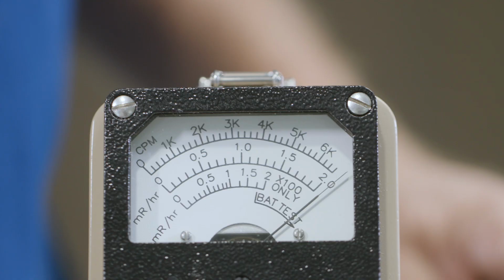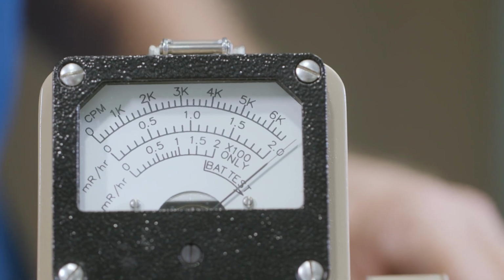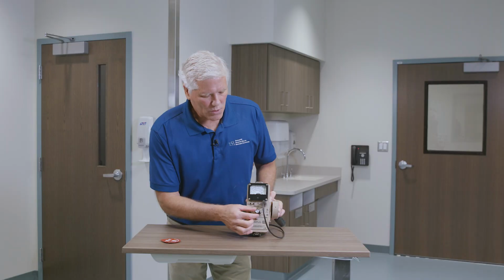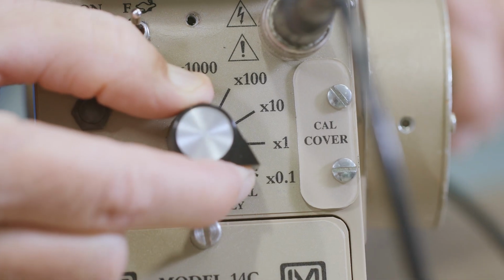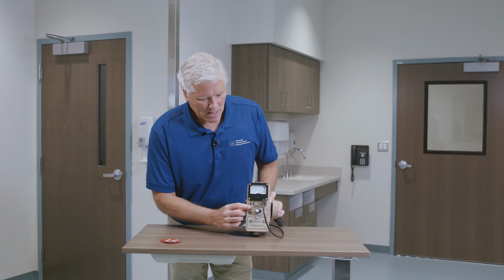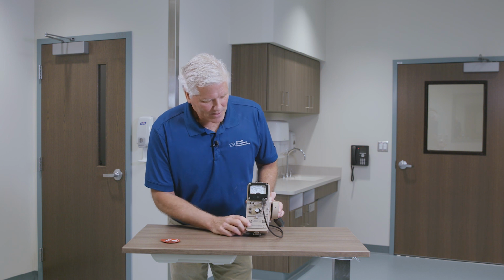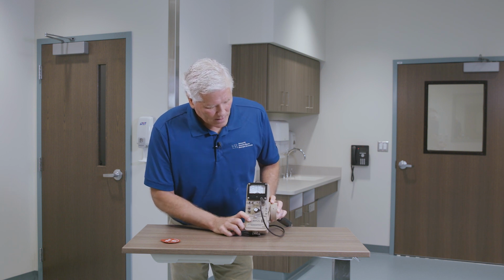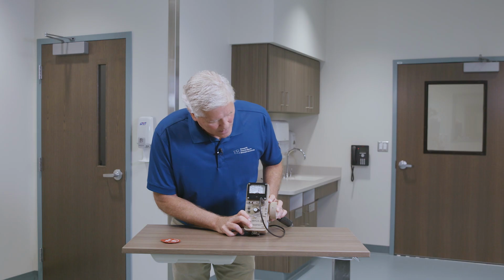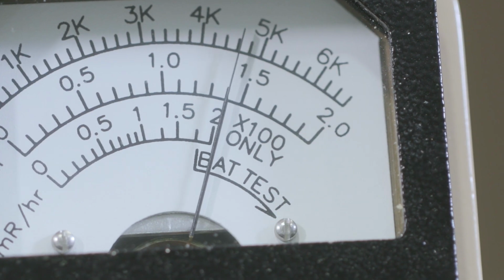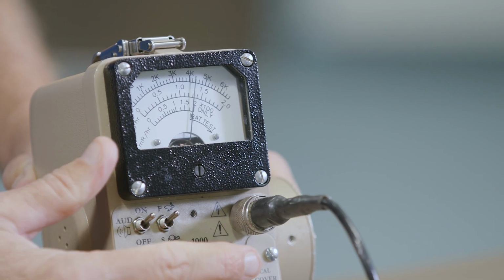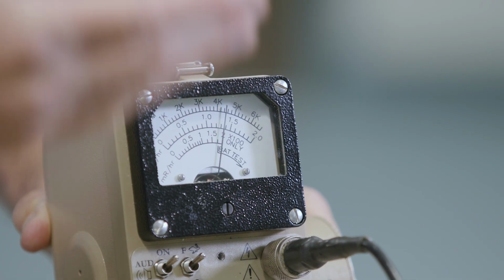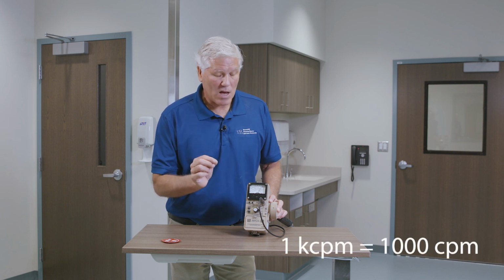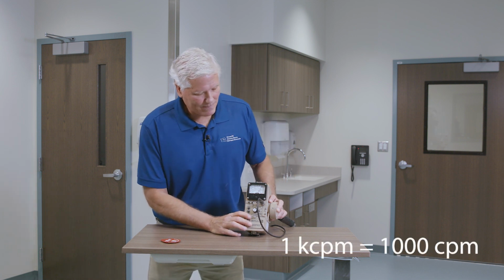And we can see that the needle deflected off scale, which means we need to go to a higher scale. So we're going to move from times 0.1 to times 1. I'll go ahead and hit a reset to make it go faster. And you can see that it's reading up around 5K. Remember, we're on the times 1, so this makes it easy. So we'll take 5K times 1, or it's 5K counts per minute. And remember, the small k stands for 1,000, so 5,000 counts per minute.